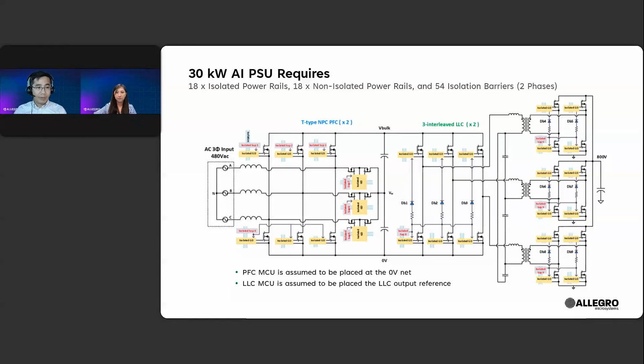This is the level of complication we need to deal with. Here is the schematic of the PSU with three-phase 480 volts AC input. The PFC uses a T-type neutral point clamp topology to rectify the AC input and boost the voltage up to around 800 volts. This T-type NPC topology is similar to the Vienna rectifier, except that the 1200 volt silicon carbide diodes are replaced by 1200 volt active switches for conduction loss reduction. As a result, the T-type NPC needs 6 isolated gate drivers for the boost switches, in addition to 3 isolated gate drivers for the bidirectional back-to-back switches.